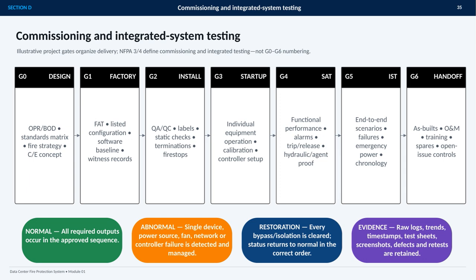G5 is integrated system testing, using end-to-end scenarios that include failures, emergency power, and event chronology. Finally, G6 confirms handoff through as-builts, operations and maintenance materials, training, spares, and open-issue controls. The critical point is that G0 through G6 are illustrative project gates. NFPA 3 and NFPA 4 define the commissioning and integrated testing practices, not this numbering system. Evidence should cover normal operation, abnormal conditions, and restoration, with logs, trends, timestamps, test sheets, screenshots, defects, and retests retained.